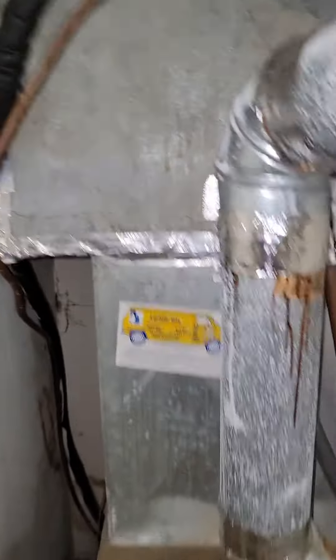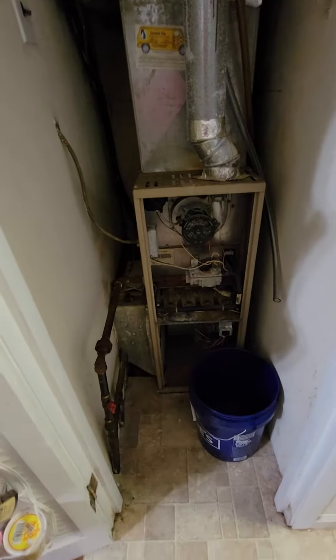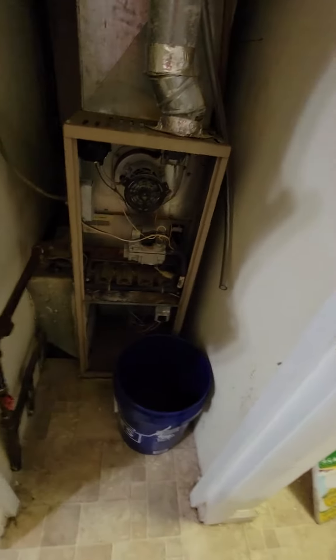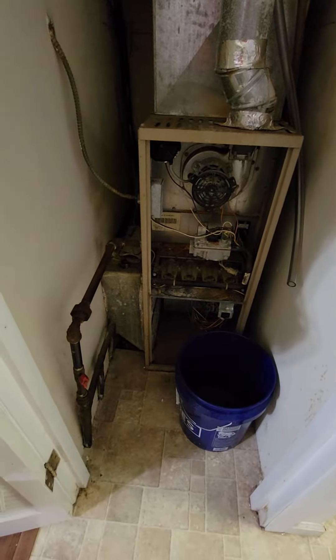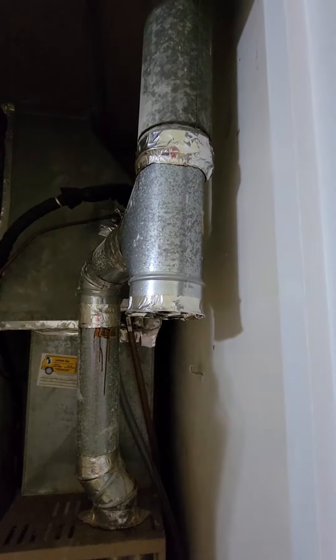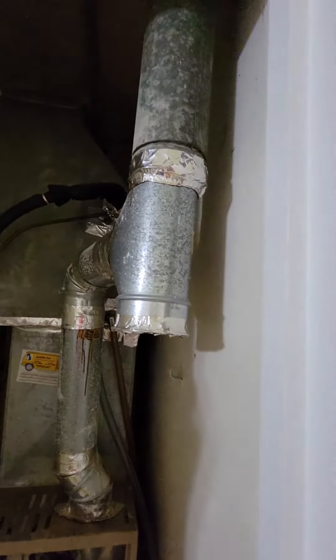So I think we're stuck in a closet here. But anyways, we would do the furnace. We can cut to the left — that's just sheet metal going to the return drop. So we can cut that back and just do a one-inch filter in between. Then we can redo the gas line as needed. We'll need new venting — it's a four-inch flue, so a four into a four. That should line up and that should be everything.